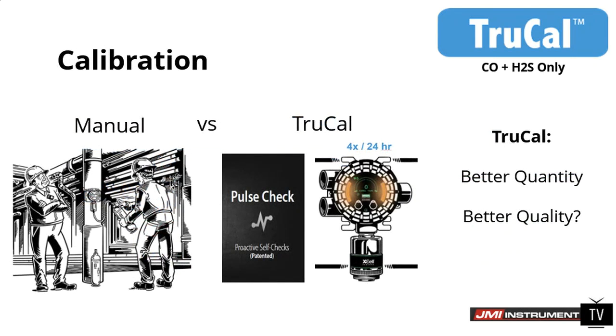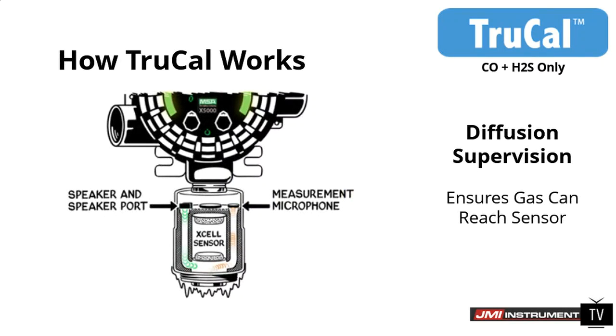So when we talk about manual versus TrueCal, which one would you guys rather see? Would you rather be doing your own calibrations every 3 months, or would you rather be able to extend your calibrations out? Because with this TrueCal function and the pulse check, with this function alone, you can push calibrations out to 1 year without having to do a quarterly calibration. And we can push that out even farther, moving into this next portion.